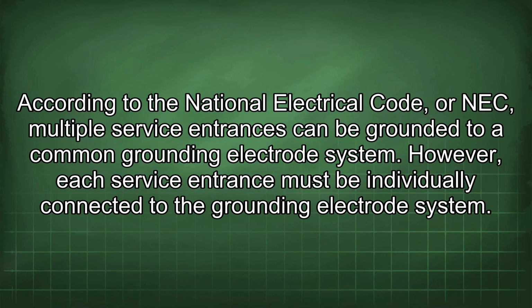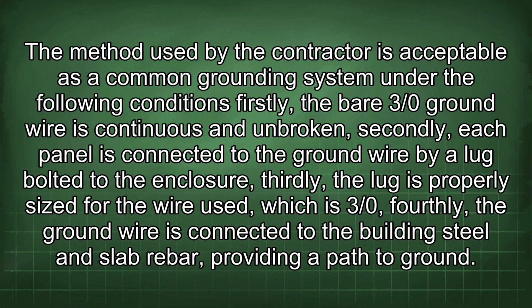According to the National Electrical Code, or NEC, multiple service entrances can be grounded to a common grounding electrode system. However, each service entrance must be individually connected to the grounding electrode system. The method used by the contractor is acceptable as a common grounding system under the following conditions.